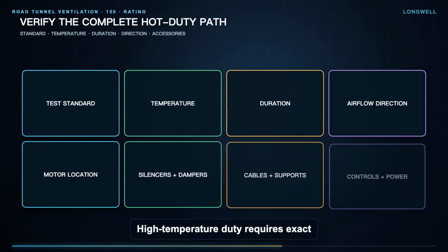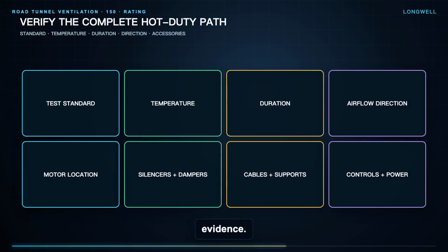High temperature duty requires exact evidence. Verify the test standard, temperature, duration, airflow direction, motor location, silencers, dampers, cables, supports, controls, and power path for the specified configuration. One component cannot lend its rating to another.